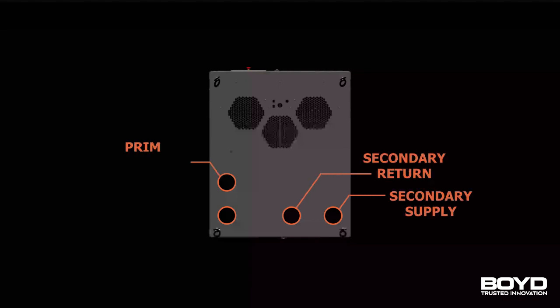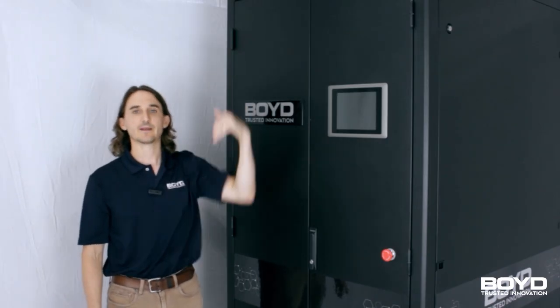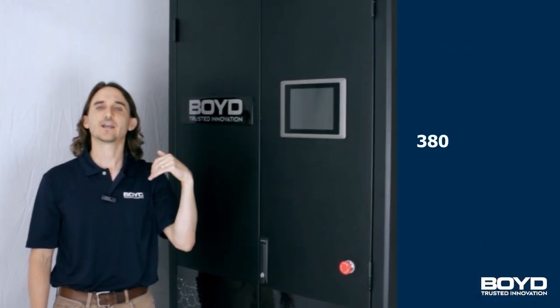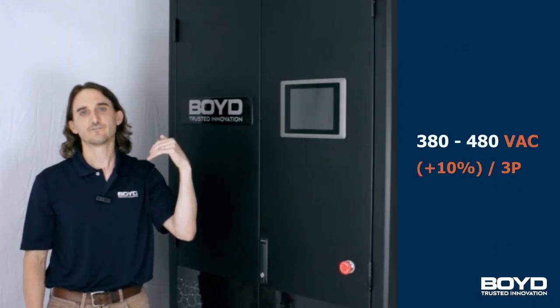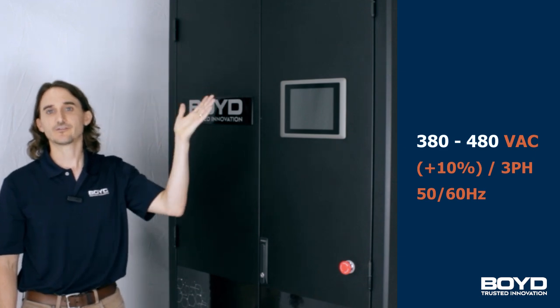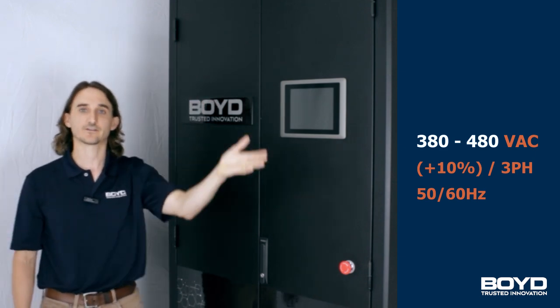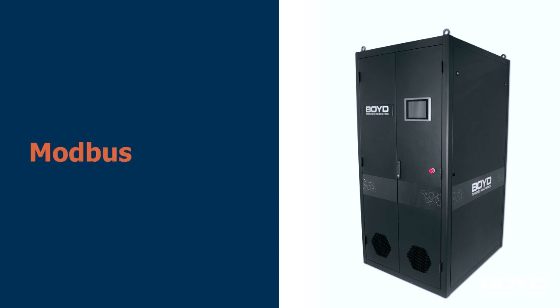On the top, which you can't see from this view, there are 4-inch tri-clamp connections to connect to overhead manifolds. These are very simple to install, and that's your secondary supply, secondary return, primary supply, and primary return. Also on the top of the unit is where the main power feed comes in. This is 380 to 480 voltage AC, 50 to 60 hertz. We also have our Ethernet connection on the top of the unit to go back to the facility. That is where the Modbus serial, Modbus TCP/IP, or BACnet protocols are communicated with the facility.